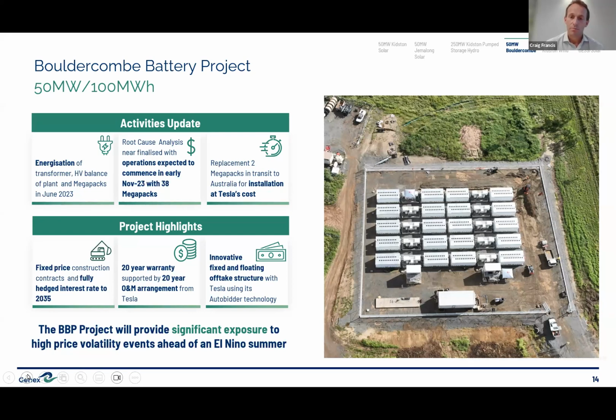It was subsequently observed that, due to the high temperatures of the exposed Megapack, there was some damage to thermal insulation on the adjacent Megapack, which is about 200 millimetres separated from the other unit. So the decision we've taken, alongside Tesla, is that they've shipped two replacement Megapacks to Australia — they're on a boat on their way — and the plan is to recommence operations with 38 Megapacks.